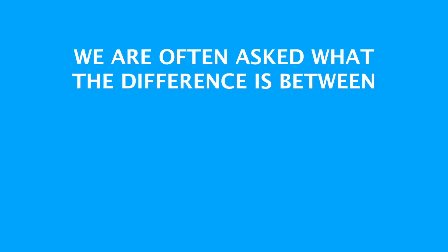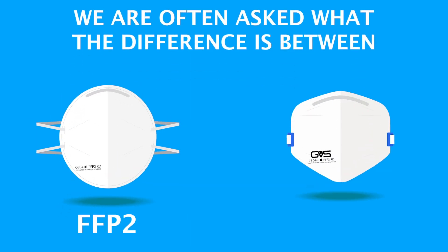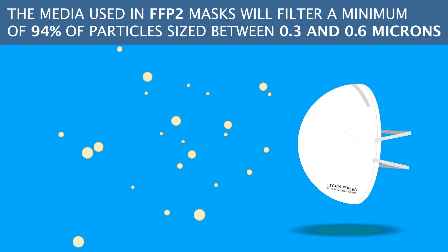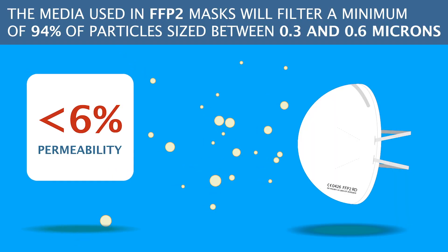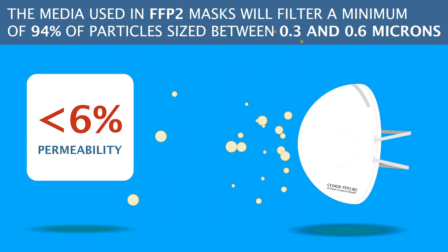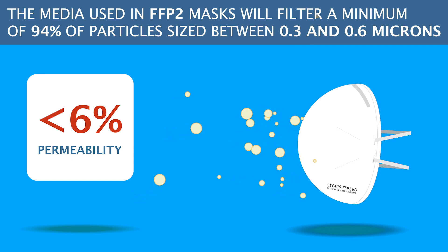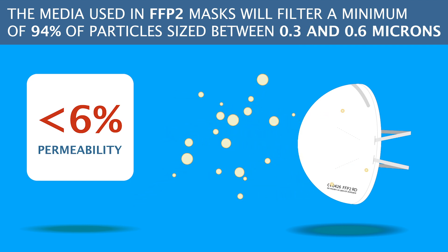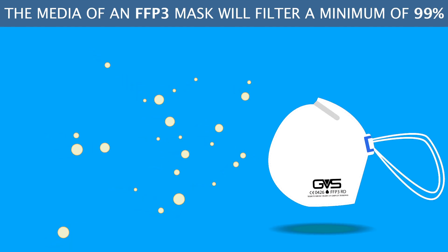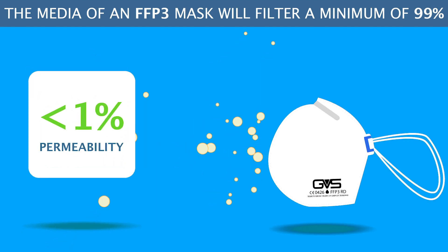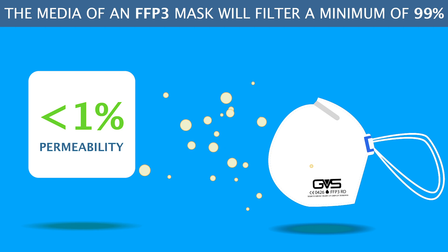We are often asked: what is the difference between an FFP2 and an FFP3 mask? There are several things you should know. The media used in FFP2 masks will filter a minimum of 94% of particles, sized between 0.3 and 0.6 microns. The media of an FFP3 mask will filter a minimum of 99%.